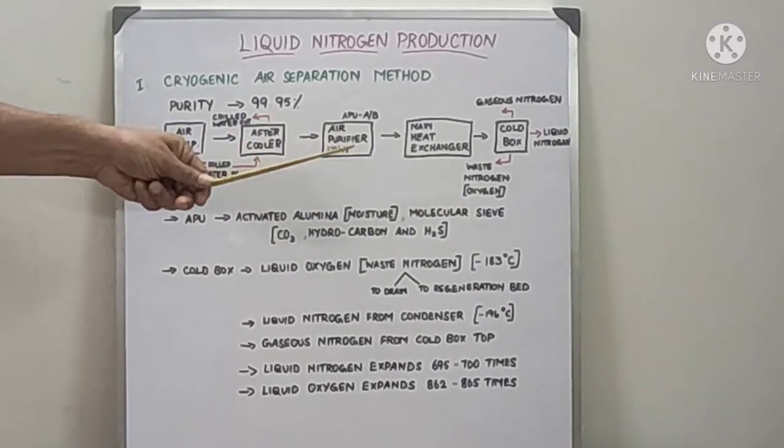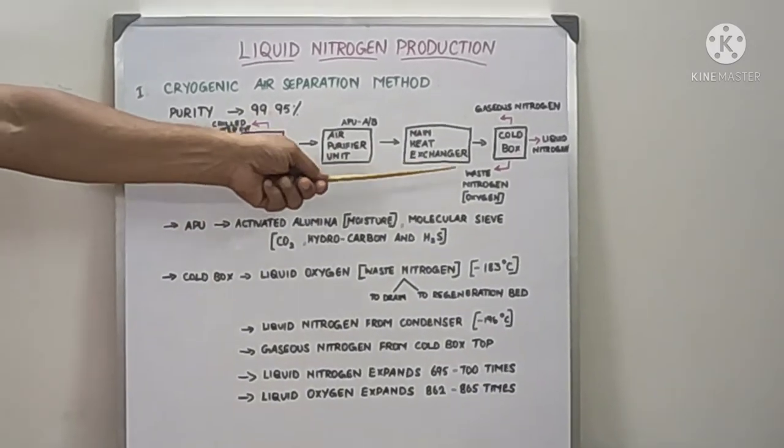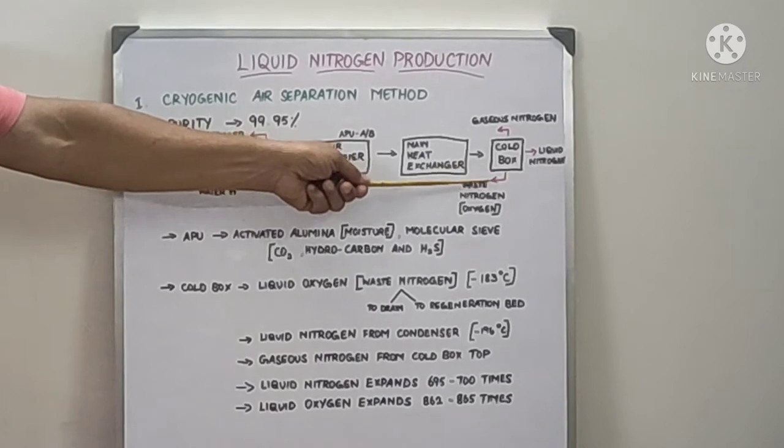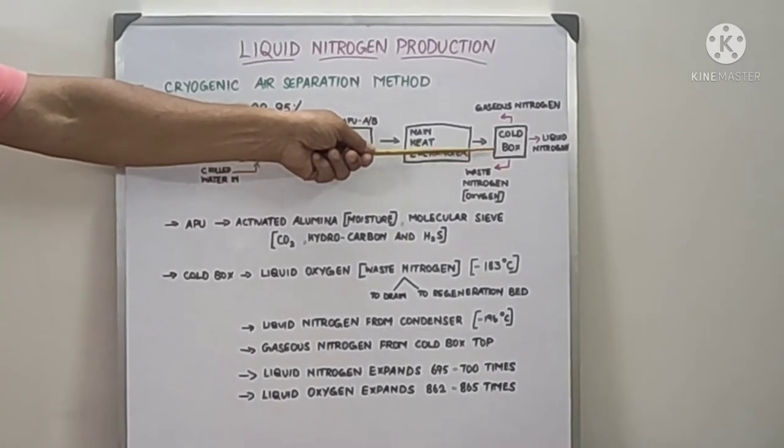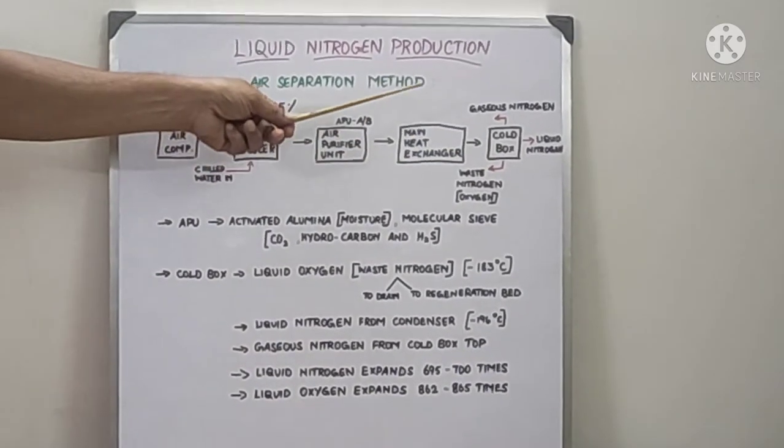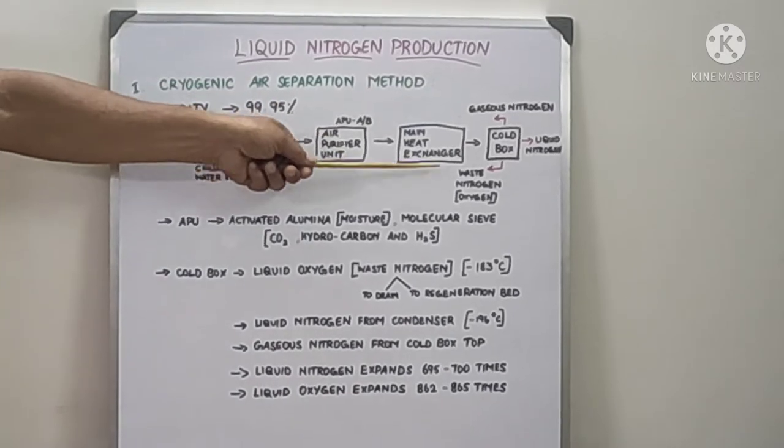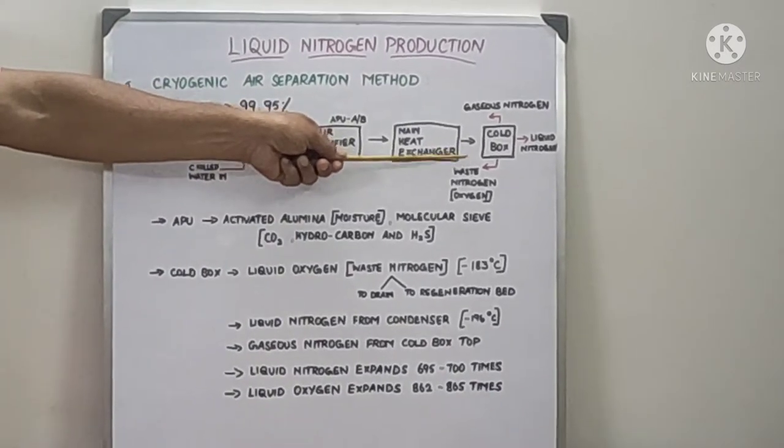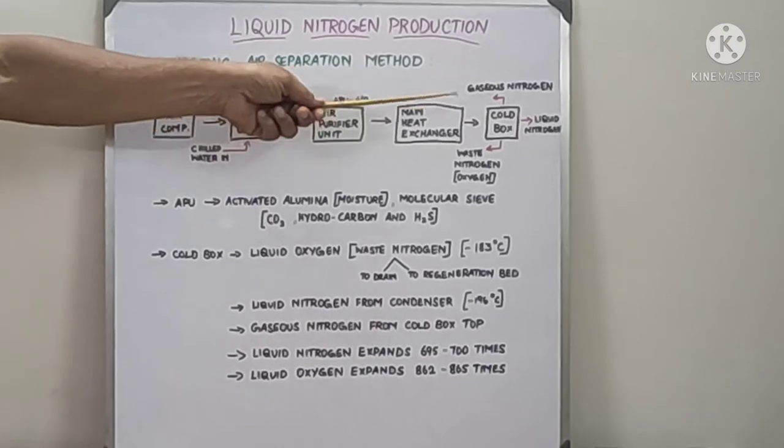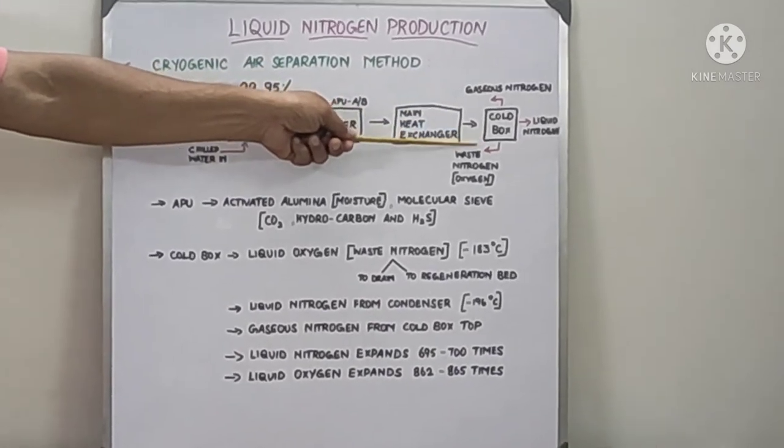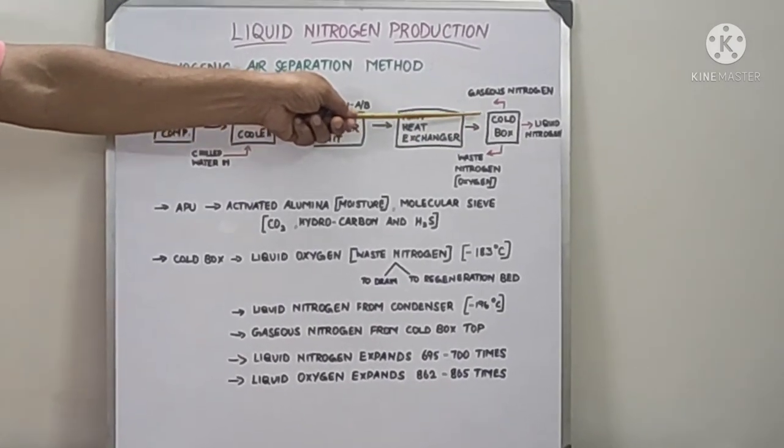For the beginning of start-up, we will have some liquid nitrogen to get cooling effect or cold energy. If you don't have nitrogen, then the process will take more than two days. Air will be circulated, then cooling is affected by means of Joule-Thomson effect and the temperature is attained.